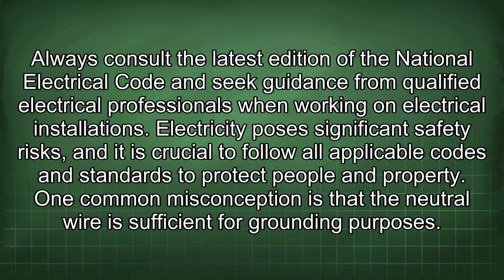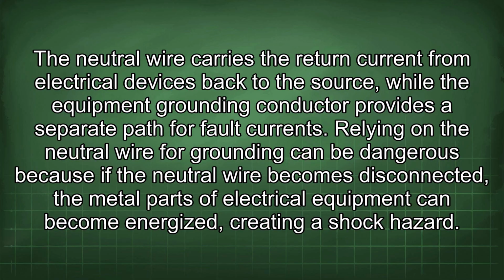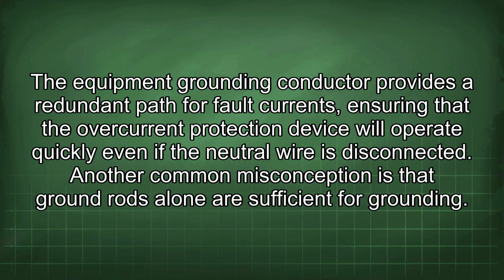One common misconception is that the neutral wire is sufficient for grounding purposes. The neutral wire carries the return current from electrical devices back to the source, while the equipment grounding conductor provides a separate path for fault currents. Relying on the neutral wire for grounding can be dangerous because if the neutral wire becomes disconnected, the metal parts of electrical equipment can become energized, creating a shock hazard. The equipment grounding conductor provides a redundant path for fault currents, ensuring that the overcurrent protection device will operate quickly even if the neutral wire is disconnected.